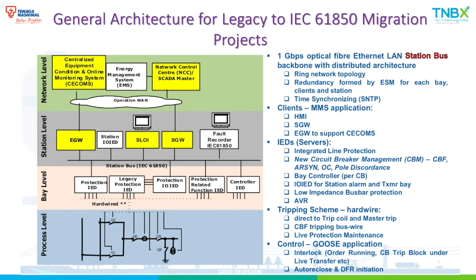This will be the guideline for migration projects, where hardwire connections are still present for tripping functions. GOOSE application, however, will be fully implemented for interlock and auto-reclose, as well as for digital fault recording initiation functions.